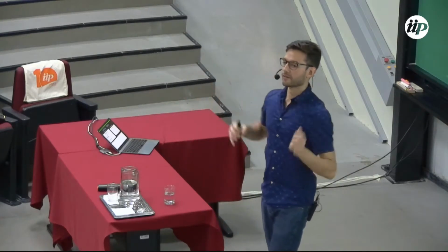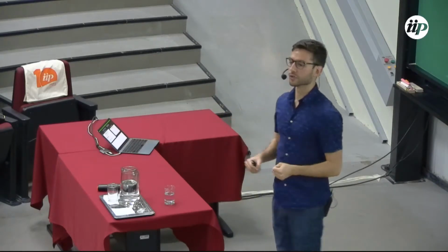In an ideal world, we would have our own sources of gravitational waves. We would put them right over the instrument, we know exactly what the strain is, we look at the output, and we can tell exactly, this much voltage, this much strain. We cannot make our own gravitational waves for reasons I hope you appreciate. But what we can do is to just push the mirrors, okay? And we can do so using radiation pressure. So we have a system of auxiliary lasers called Pcal lasers, for photon calibrators. These are different from the main lasers of the interferometers that I discussed last time.